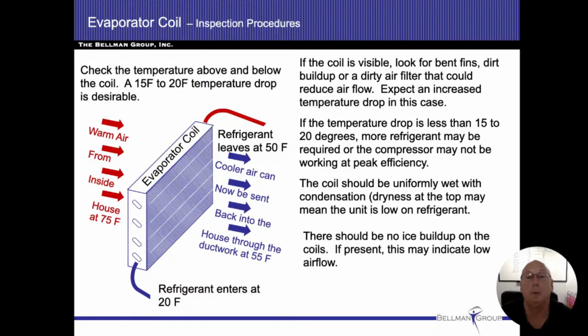The coil should be uniformly wet with condensation, and you're only going to see that on the underside. You're not going to see that on the top side. Definitely there's not going to be any ice buildup. If we see ice anywhere, whether it's on the refrigerant lines, on the coil itself, we're low on refrigerant. All right, so ice buildup is going to be the number one indicator for low refrigerant.